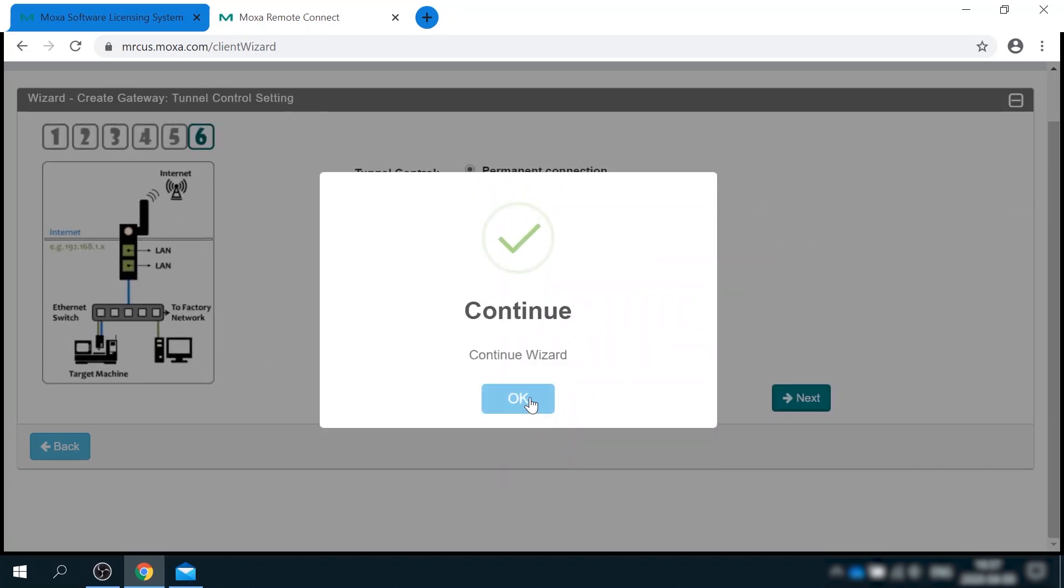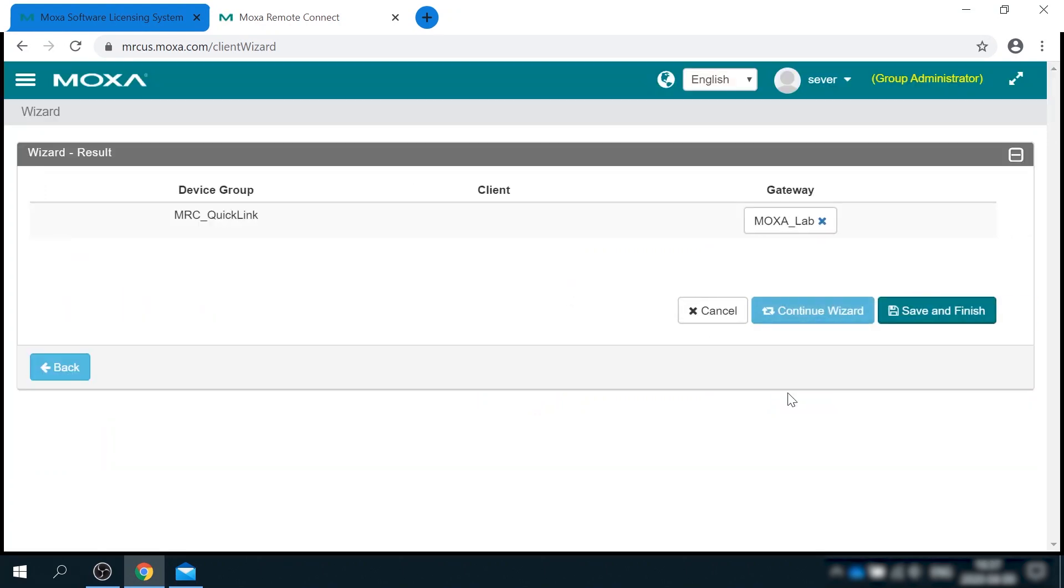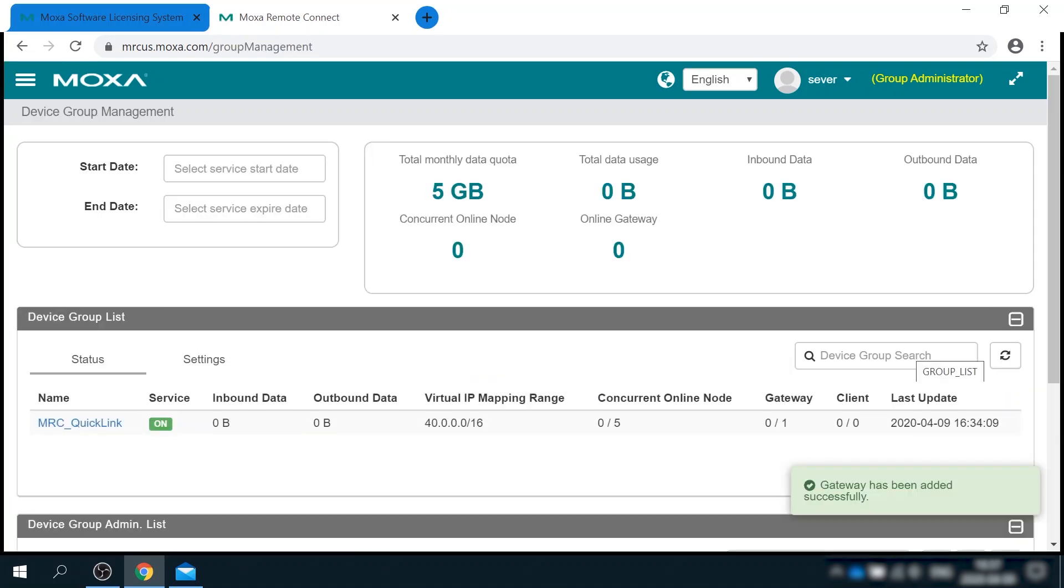And the final step is tunnel control. Here I can define whether gateway will have permanent connection to the cloud or controlled by the presence of USB key or digital input. Let's select USB here. And we are done with gateway setup.